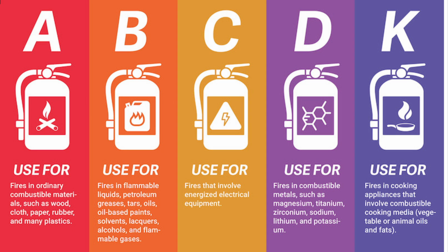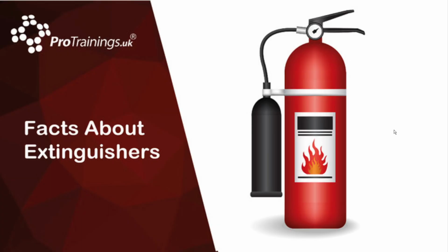Unlike stored pressure types, these extinguishers use compressed carbon dioxide instead of nitrogen, although nitrogen cartridges are used on low temperature, -60 rated models. Cartridge operated extinguishers are available in dry chemical and dry powder types in the US, and water, wetting agent, foam, dry chemical classes ABC and BC, and dry powder class D types in the rest of the world.